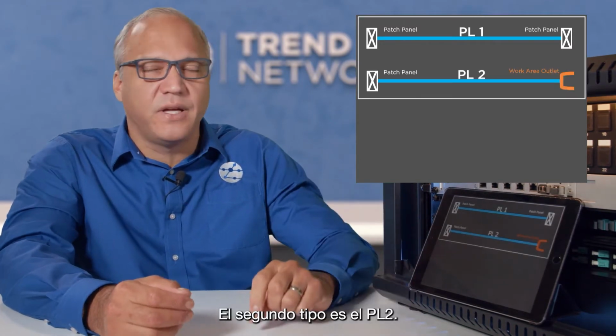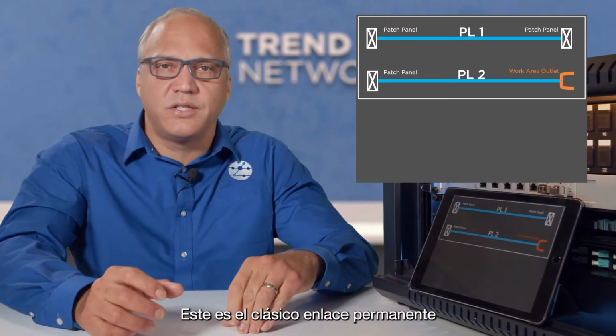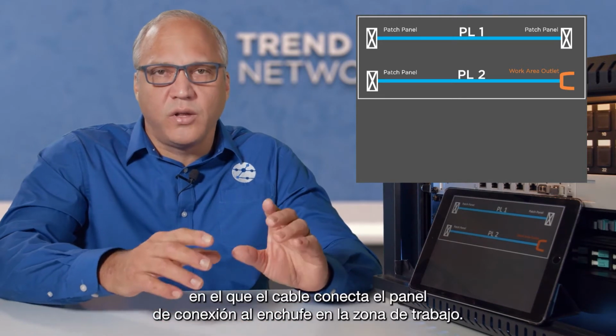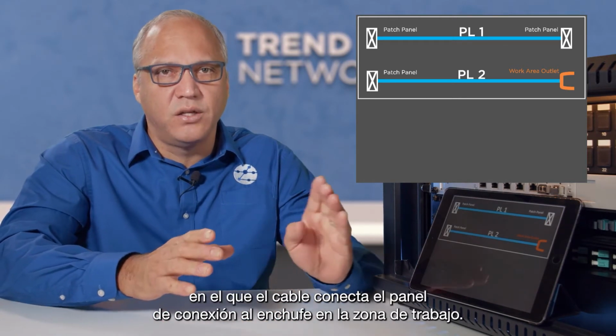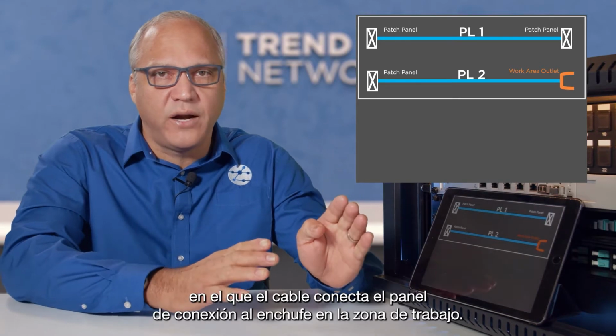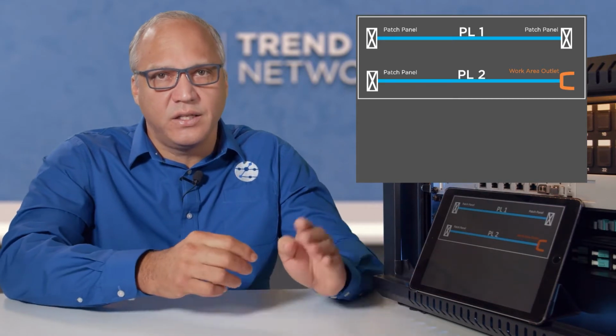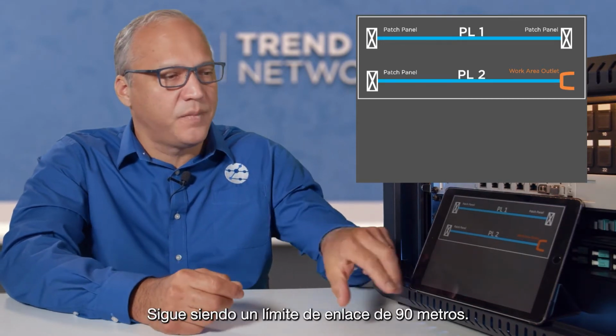The second type is the PL2. So this is your classical permanent link where the cabling is going from the patch panel to the work area outlet at the other end. Still a 90-meter length limit.